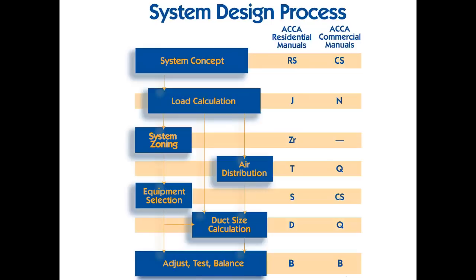In an ideal world, an HVAC system designer would follow the full ACCA design process, which you can see here in the diagram. The boxes on the left are the general steps: system concept, load calculations, system zoning, air distribution, equipment selection, duct sizing calculation, and adjust, test and balance. The boxes in the middle are the corresponding residential ACCA manuals, and on the right column are the corresponding commercial ACCA manuals. For this introductory video series, we'll be focusing on the load calculation, which is this video; the equipment selection, which is the next video; and duct sizing, the third video. These are the core steps for proper HVAC design, and not surprisingly, the minimum code requirements.